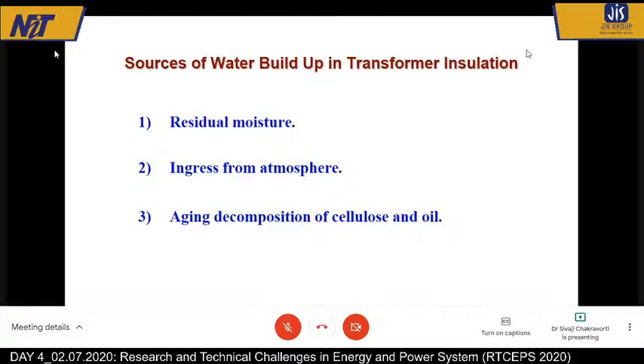But all this said and done, what will happen if moisture is generated within the transformer? Nothing can be done. And that is actually the primary concern, that due to aging, moisture is generated inside the transformer. And then that remains within the transformer and damages all insulation. So what we are talking about today is that part of the moisture which is generated as a part of aging.